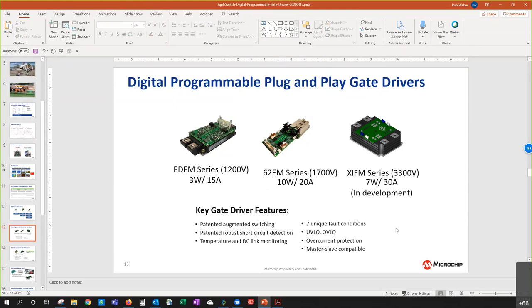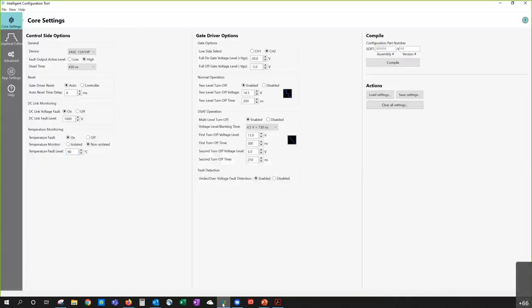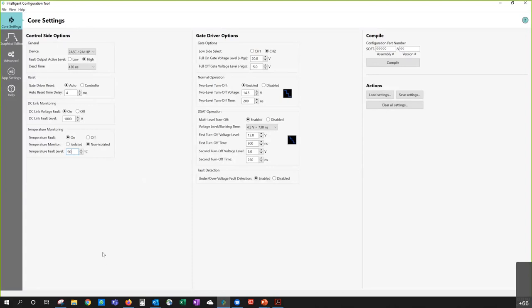Okay. What is the lowest setting for short circuit? Okay, so I'm assuming they're talking about the blanking time or the reference voltage. Reference voltage obviously is dependent on the device, but for blanking time we can go as low as 500 nanoseconds. In experimentation, of course in a lab setting, we've been able to detect short circuit at 500 or 600 nanoseconds, with the total turnoff time being less than one microsecond. But typically, going into production, most customers choose an 800 to 900 nanosecond window for detection, with the total turnoff time being less than 1.5 microseconds.